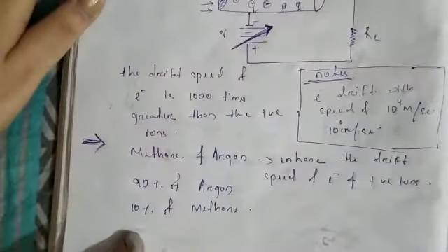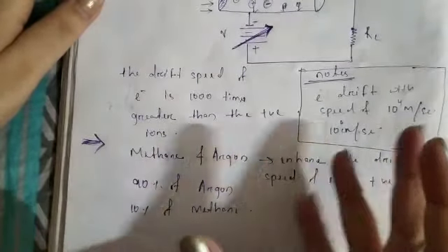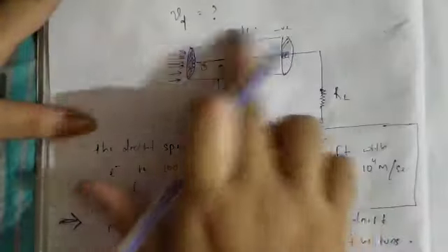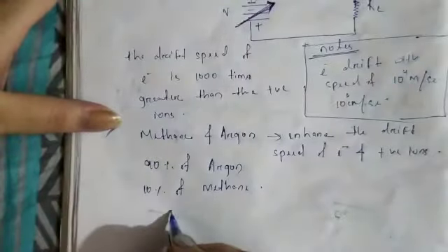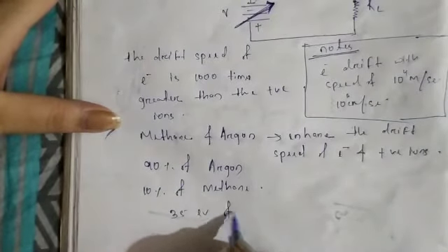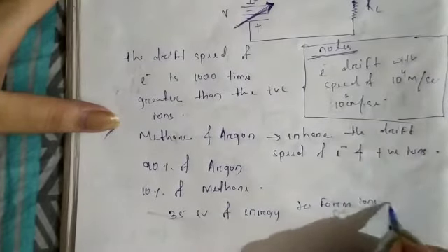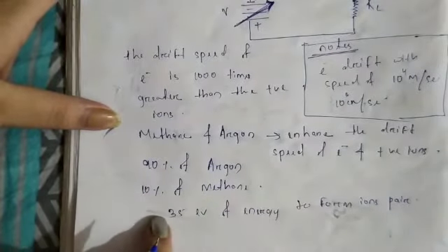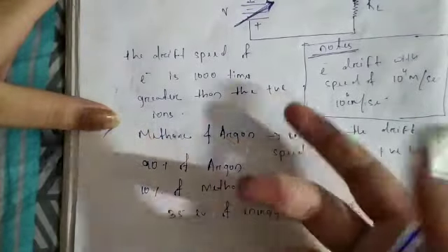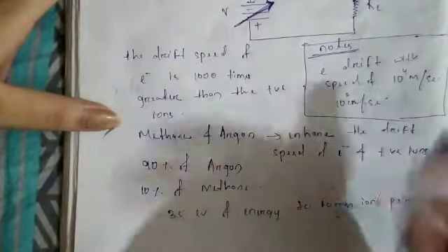Another point to remember is that experimentally it is found that 35 electron volt of energy is needed to form an ion pair in air. If you consider the gas as air, it needs 35 electron volt of energy to form an ion pair. So if the particle loses 1 mega electron volt, or 1 MeV, the ionization chamber forms 2.86 into 10 to the power 4 ion pairs.